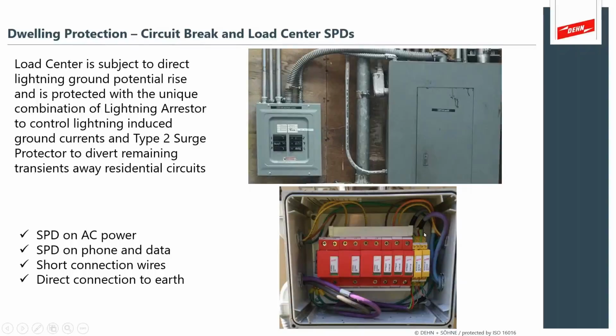You also want to pay attention, some manufacturers include surge protection with their panel. In the event of that having something that looks like the catastrophic failures we saw early on in our photographs, you want to consider having the surge protection device next to, but not inside of the same panel. That's preferenced by the application.